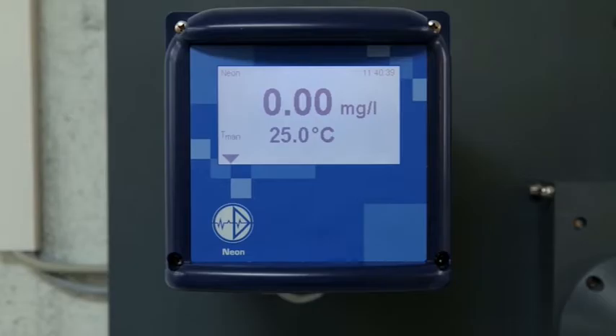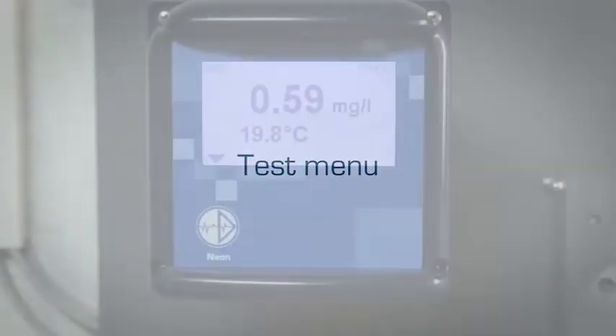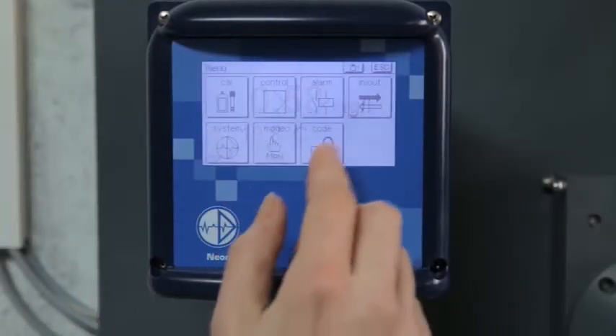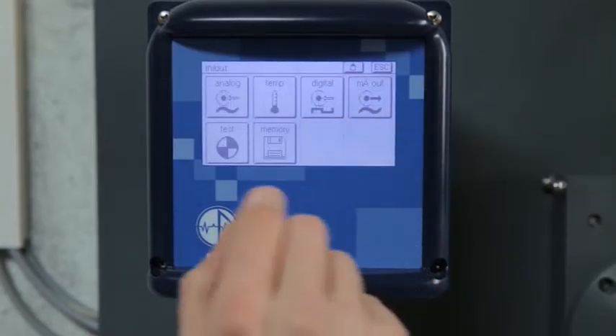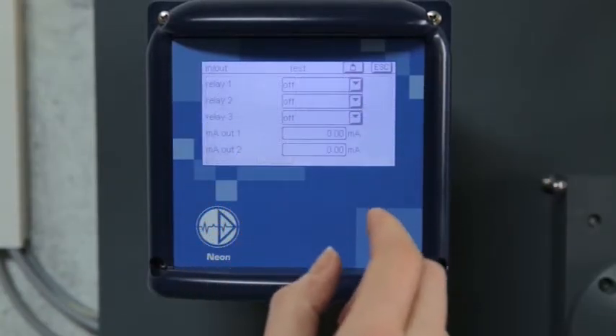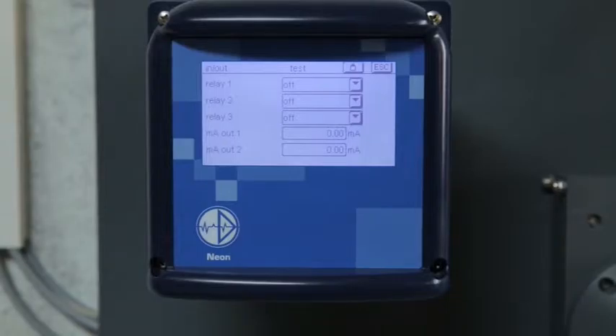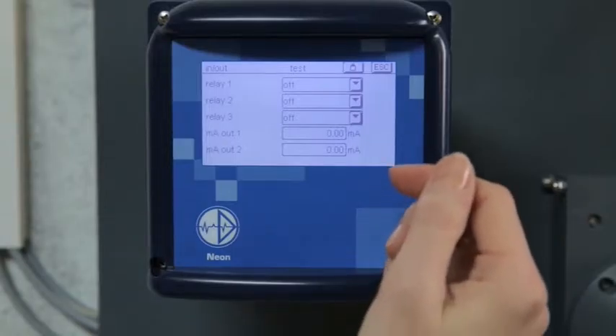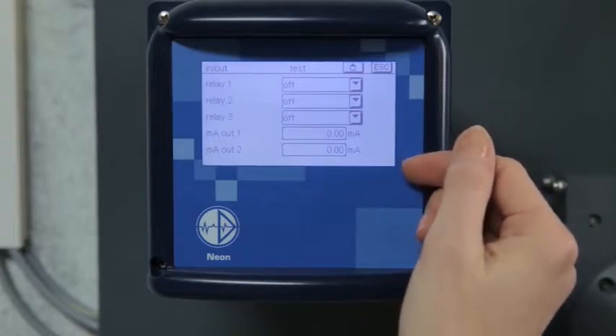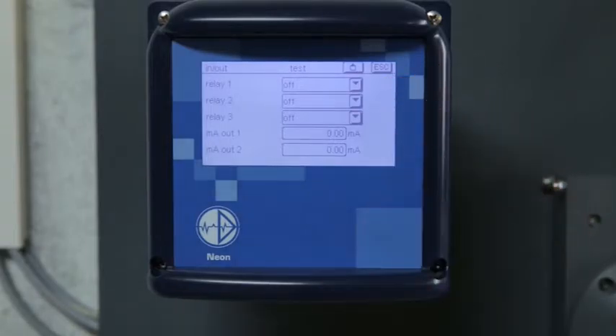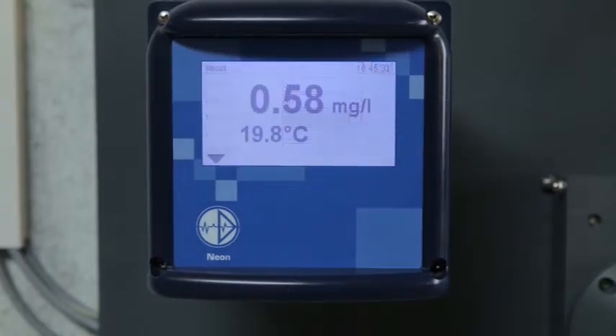When the power is switched on, the instrument starts with a self-check and displays first the time and then the measured values. All output options of the instrument can be set manually in the test menu. You can switch each relay and set values for each milliampere output to check whether the wiring is correct and the output reaches the PLC. As soon as you exit the test menu, all test settings get lost and the outputs return to their previous states.